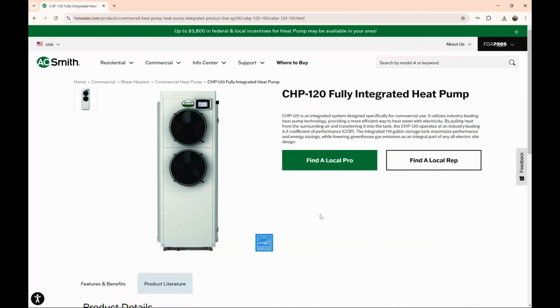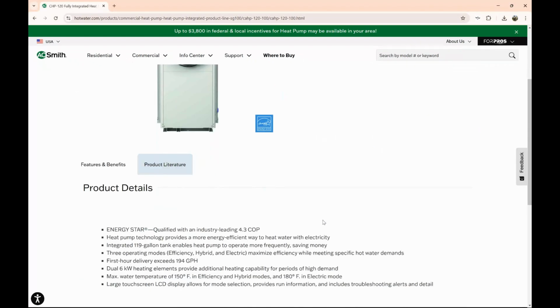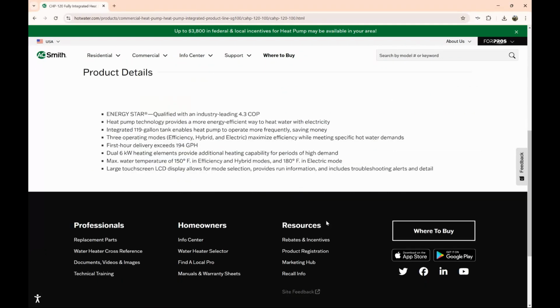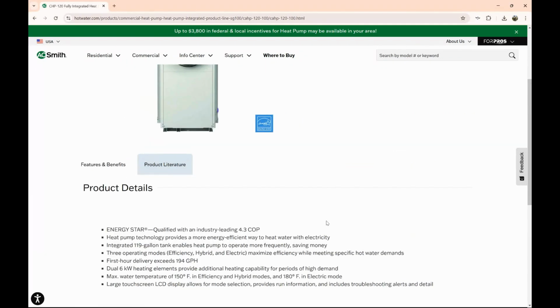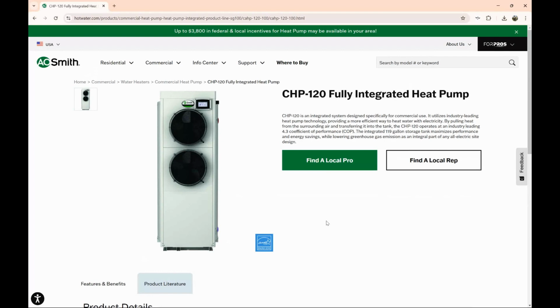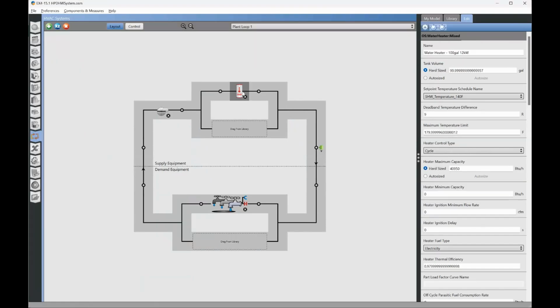It has a heat pump for heating during mild weather conditions, and then it also has a backup electric heater for extreme weather conditions when the heat pump is unable to operate. So that's what we're going to do today. We're going to replace this in our domestic hot water loop with a heat pump hot water heater. So for now, we are going to leave this one in place.